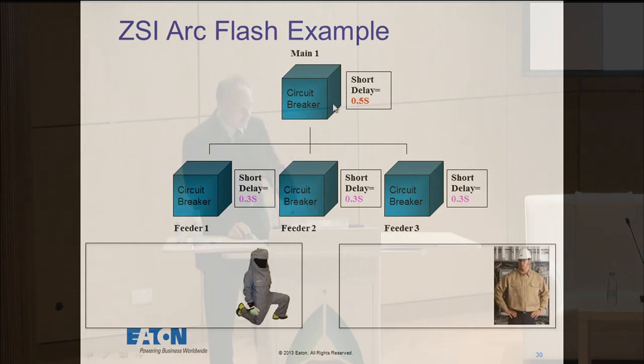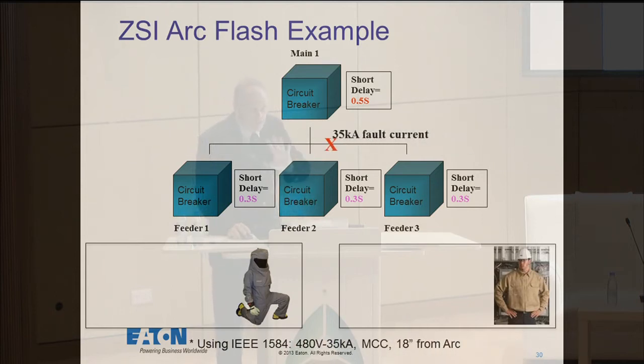This is an example here, and again, it's the same very simple example: at the top, a main breaker. Its short delay setting is set at a half a second. These are set for 0.3 second, and there could be many more down in the system that cascade down. The intention is always to make sure that the one closest to the fault opens up, right? So you set the timings of them to do so. So what happens when a fault occurs? I just picked an example on a 480-volt system, a 35 kA fault, 35,000 amp fault, which is not unusually high. This is being done using a calculation method saying that for a motor control center, the working distance they assume to be 18 inches unless you know something different.